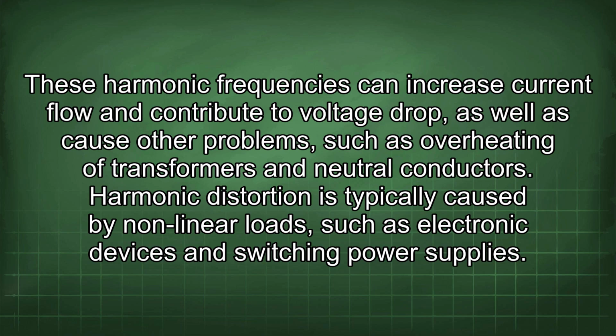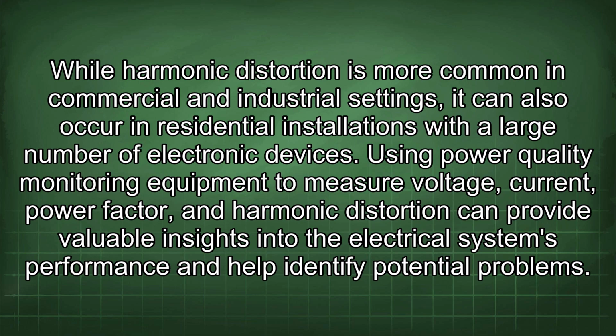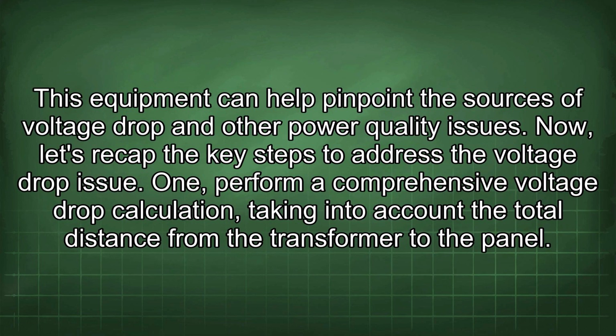Harmonic distortion is typically caused by nonlinear loads such as electronic devices and switching power supplies. While harmonic distortion is more common in commercial and industrial settings, it can also occur in residential installations with a large number of electronic devices. Using power quality monitoring equipment to measure voltage, current, power factor, and harmonic distortion can provide valuable insights into the electrical system's performance and help identify potential problems. This equipment can help pinpoint the sources of voltage drop and other power quality issues.